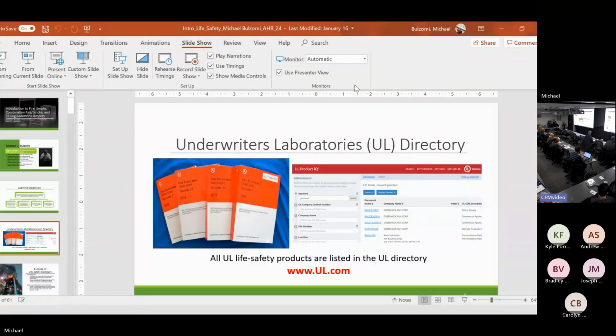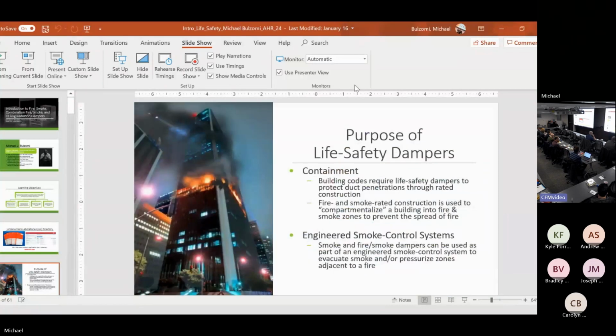You can go online to the Product iQ. Go to ul.com. You need a login, use your work or personal email. It's free. And then you can verify all the information on submittals, maximum sizes, velocities, ratings, everything's going to be in the UL directory. So that's a great way to get information. Why do we need life safety dampers?